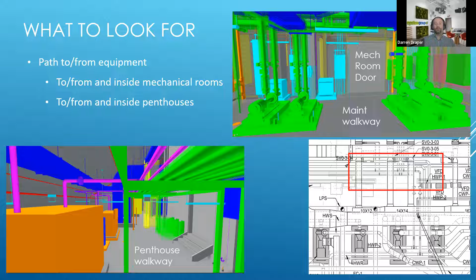This is the mechanical room door, a double door, and they created a maintenance walkway simply by pushing the pumps, splitting it 2 and 2 by services - hot water pumps and chill water pumps - creating space so you could walk through with a dolly and get a pump out or any other piece of equipment in this pretty dense mechanical and plumbing room.